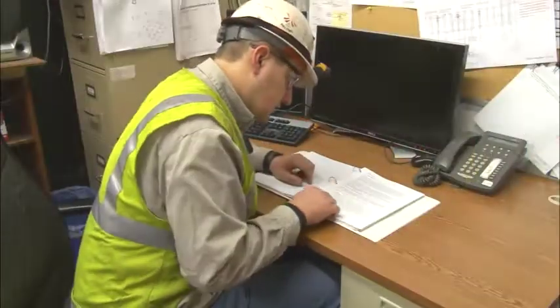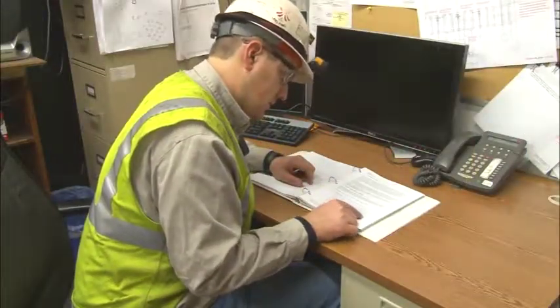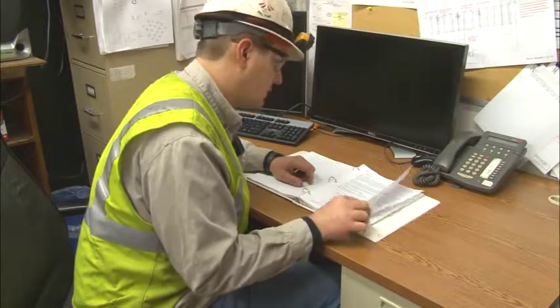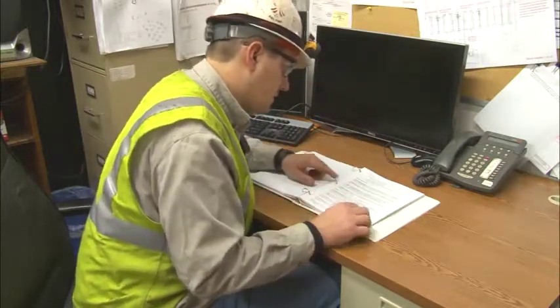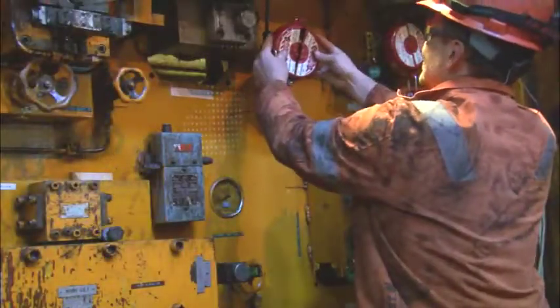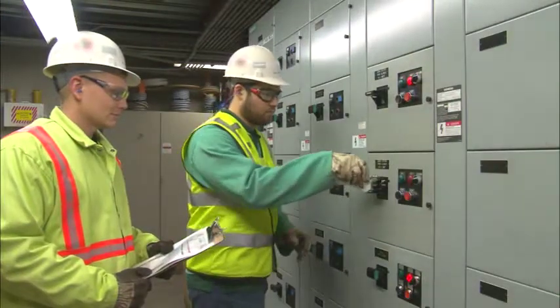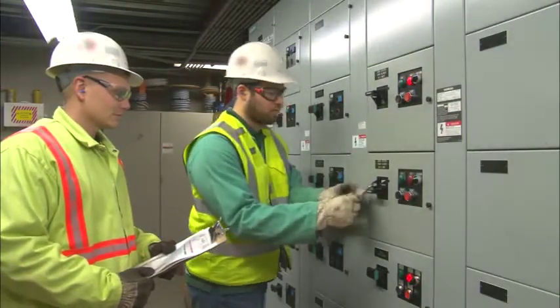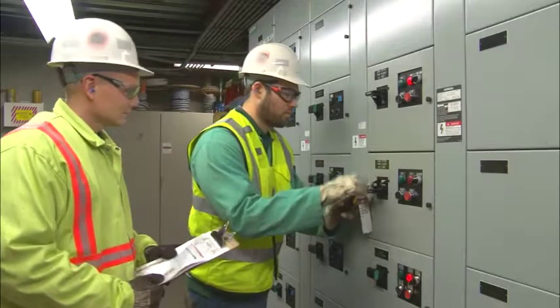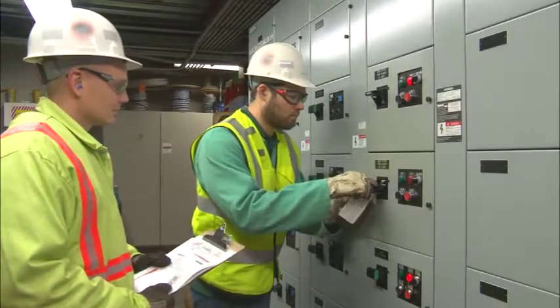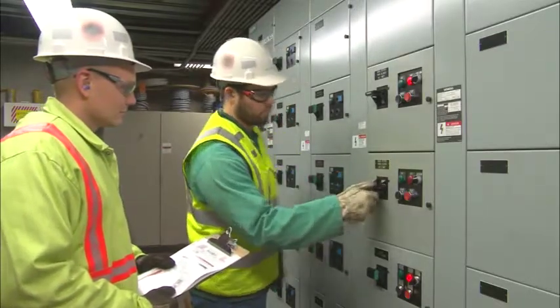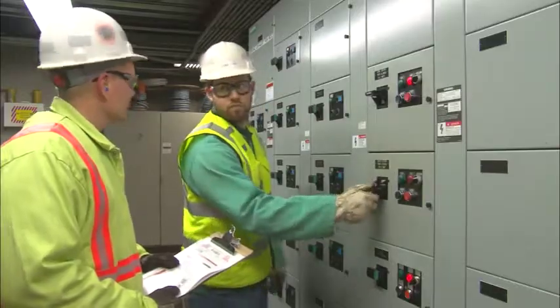In addition, energy control procedures must be reviewed annually to ensure that they are accurate and effective at isolating hazardous sources of energy. Any changes to the energy control procedures must be communicated, and authorized employees should be audited by another authorized employee when performing lockout, tagout, tryout to ensure that the procedures are being followed properly and that no deficiencies exist.